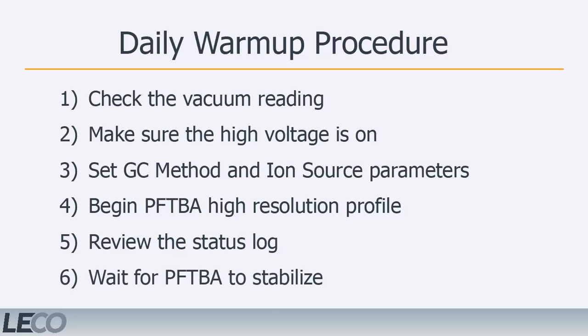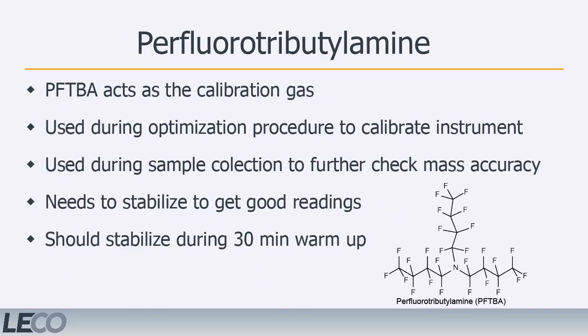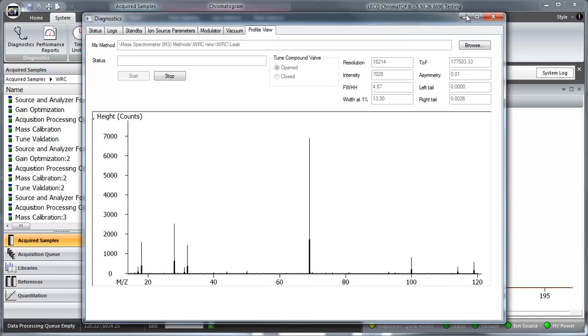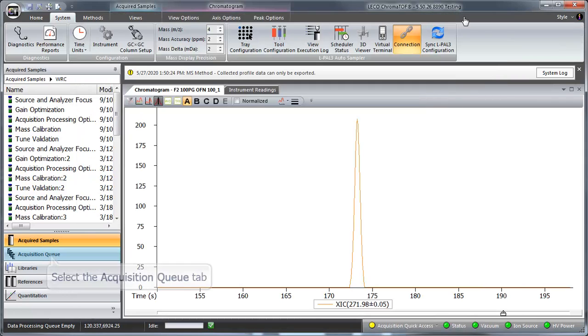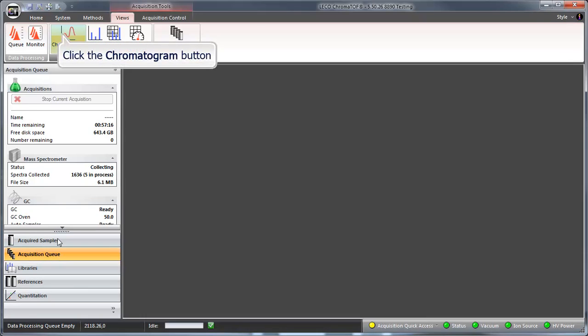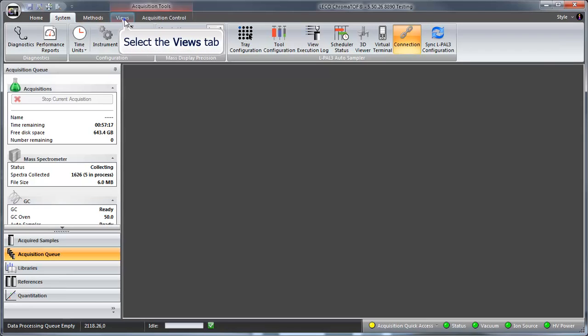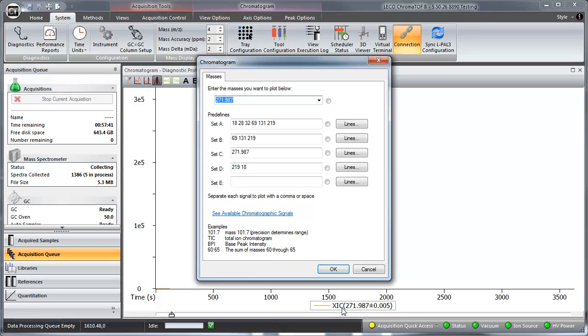Step 6. Wait for PFTBA to stabilize. The calibration gas, PFTBA, is used during the optimization process to ensure the best possible signal intensity and resolution. Because of this, the signal intensity of PFTBA must be stabilized before optimization. This stabilization can be achieved during the 30-minute warm-up cycle. To check the PFTBA stability during warm-up, minimize the Profiling tab and open a chromatogram window. Change the view to monitor fragment ions 69, 131, and 219.